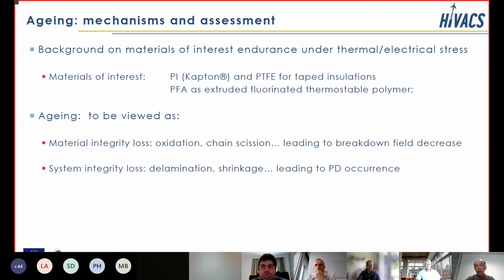The materials that we investigated, as Thomas said, are polyimide, PTFE, and PFA to be used as extruded insulation. We can see aging in two aspects. First, the evolution of material integrity, like oxidation, chain scission, etc. The other aspect is system integrity loss. If you have delamination or shrinkage, you can produce a PD when initially you didn't have any. So the tests will be achieved regarding these two aspects.